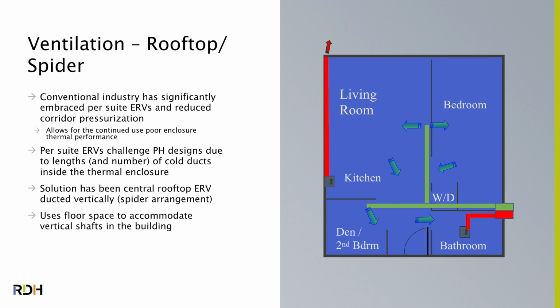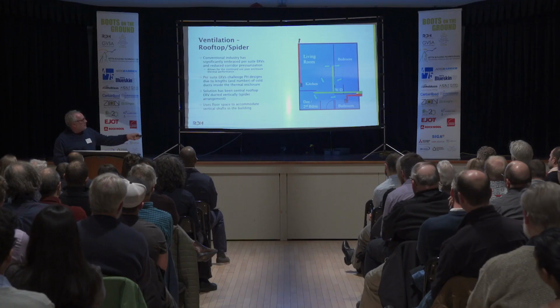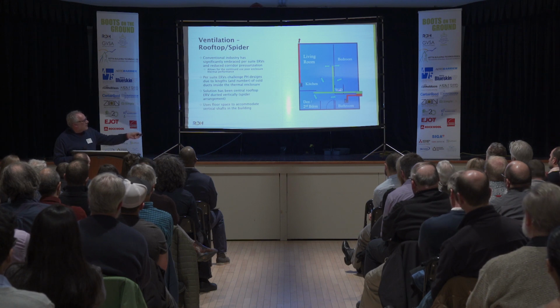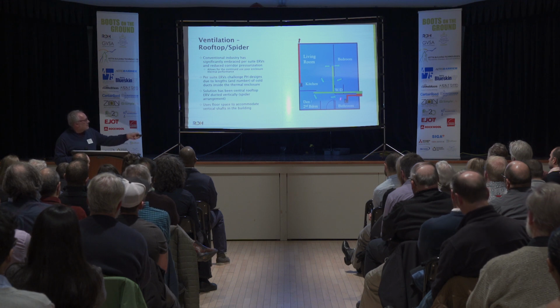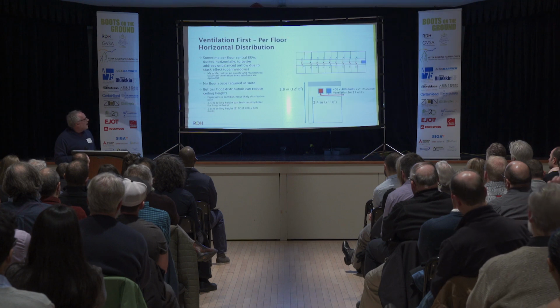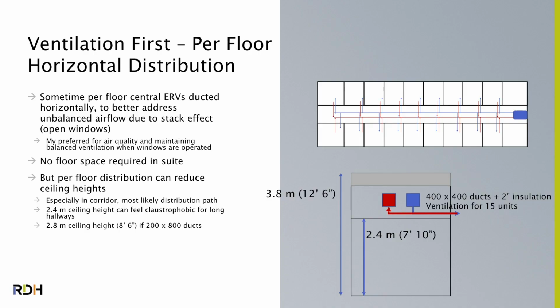So I would much rather, so you can get an idea how it would work inside the suite. You could spider it down. This would serve this in the suite next to it. Sorry, that is the ductwork, the ERV is on the roof, exhaust from the kitchen, supply to a couple spaces, air pattern through the space. I would much rather see a per floor ERV or every 2 floors ERV. This now gets rid of the stack effect issue.